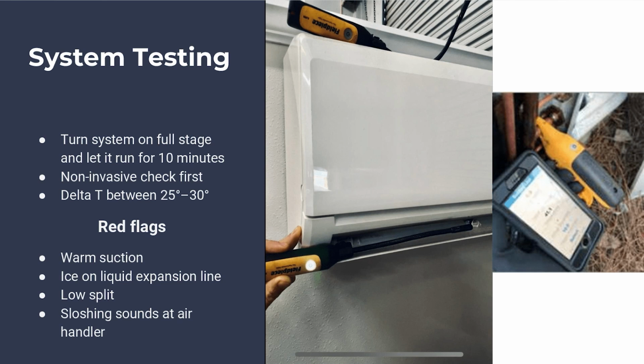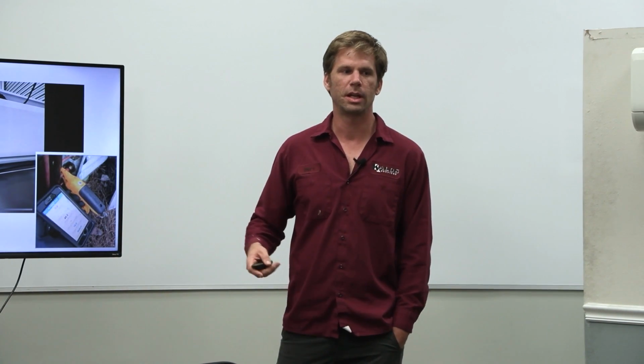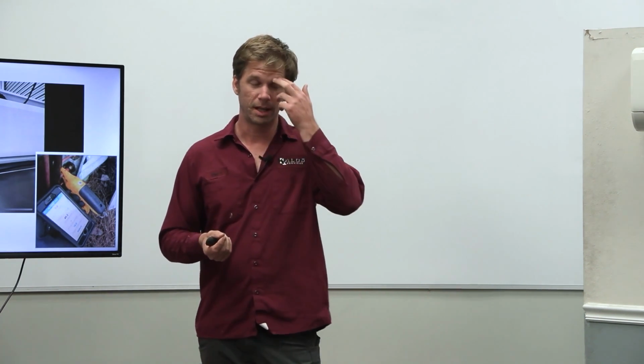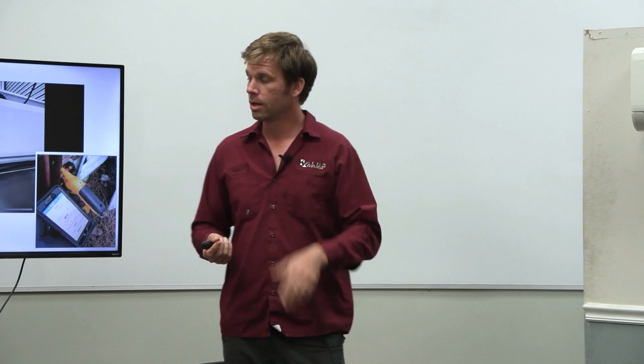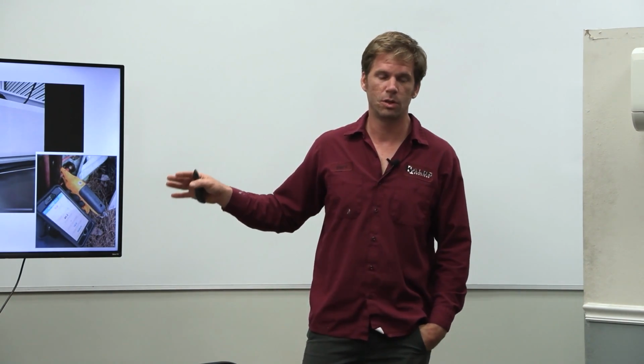Refrigerant. Okay, as you're doing this run test on the equipment, you're looking for red flags that would take you from your non-invasive check to actually needing to hook up to the system and check your refrigerant and check your superheat. Now, if you're using probes, you're not going to lose a lot of refrigerant hooking up to the system, especially if you have a proper Schrader depressor tool on the end of that or a low loss fitting. That's great. You can hook up to this, but typically when you're testing a mini split system, you don't want to hook up a gauge.